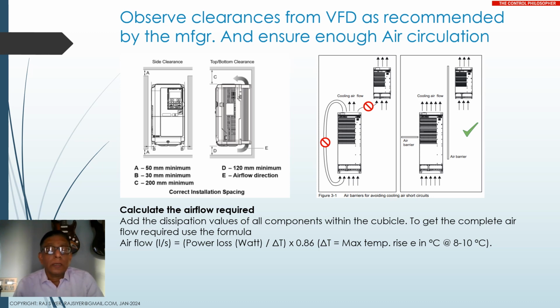Okay, now the other important thing is to calculate the airflow required for cooling. We have to not only consider the VFD, we have to consider other components within the compartment to which the cooling fan is fixed. You have to add the heat dissipation of all those components within the cubicle, and the formula for airflow is given by: airflow in liters per second is equal to power loss in watts divided by delta T, which is the increase in temperature over the ambient.